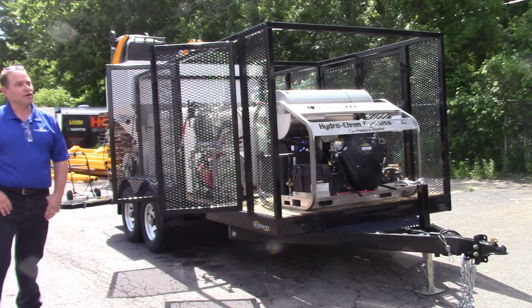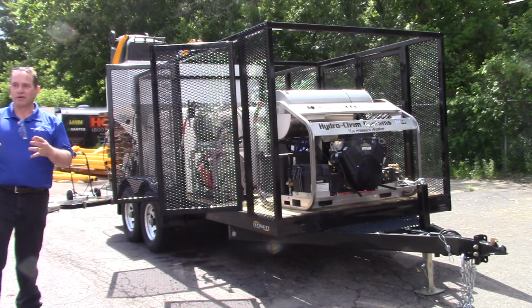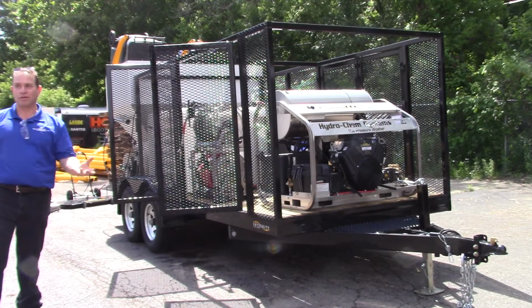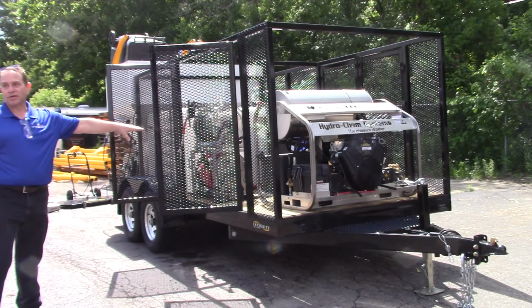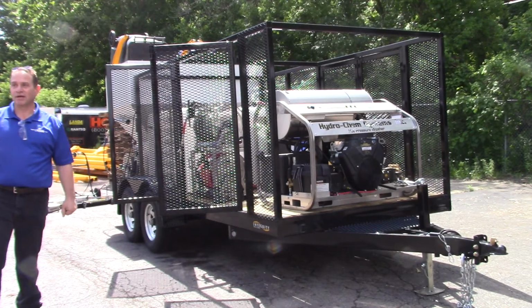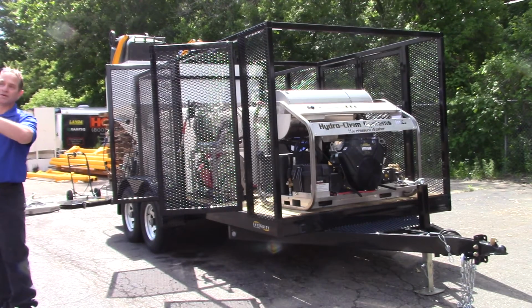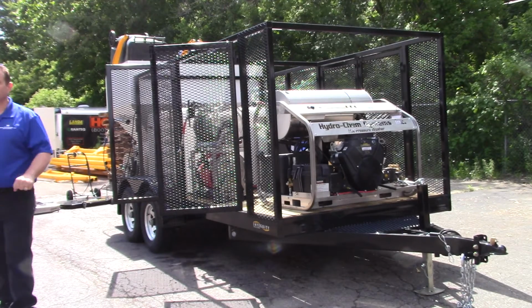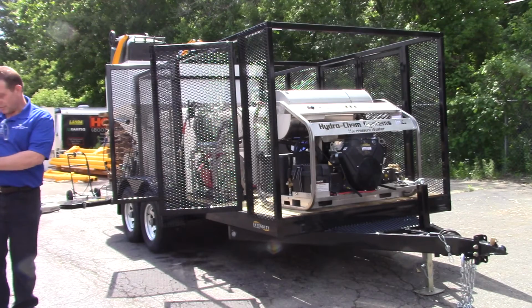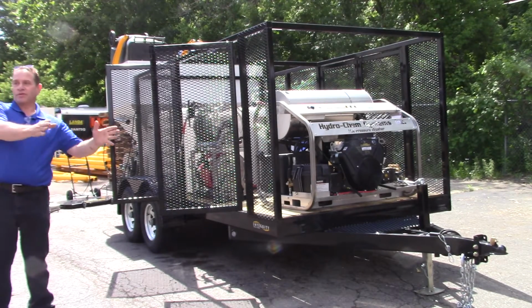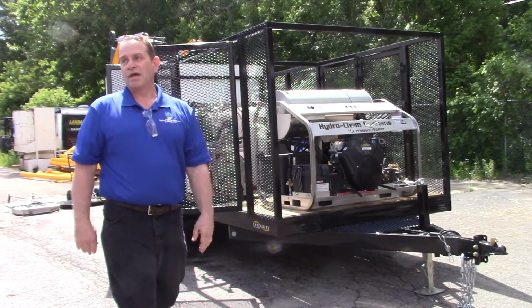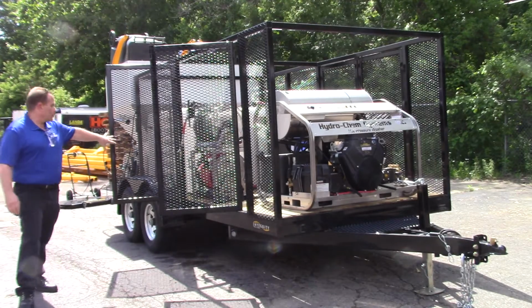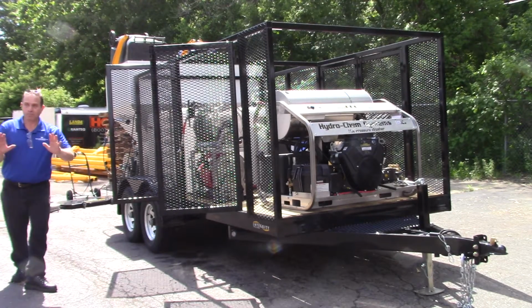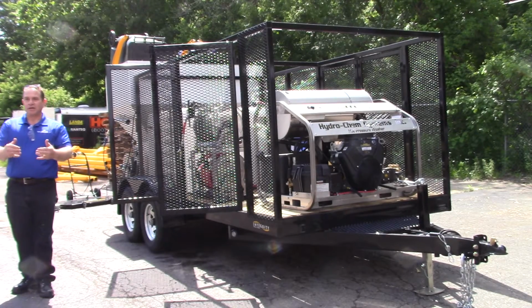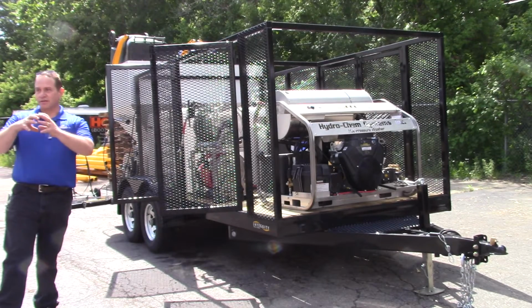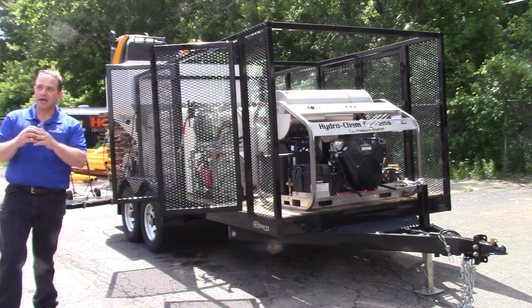What will happen that could cause that is a couple of things. If you do have a problem with your burner and you're superheating it and you've got that steam pressure, it's doing its job, it blows off. On the same token, say you go house to house with the machine running and the heat on. On occasion, there are guys that will actually follow guys through communities on sidewalks or whatever. The guy is cleaning with a 4-foot surface cleaner, and we shouldn't do that. And the guy driving the truck alongside, they're just going as they go down, keeping the hose short. It's easier to do. Well, if the water in the supply tank is a little bit too low, and they pull forward and get a little bit of air going in there, and it pushes through but doesn't completely shut everything down, then you might get this little steam burst because of the less water in there, and it could actually do a steam explosion.